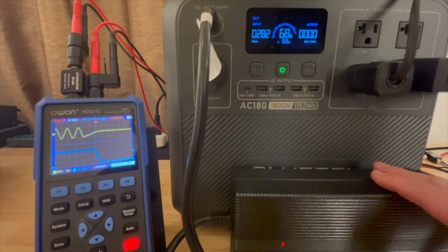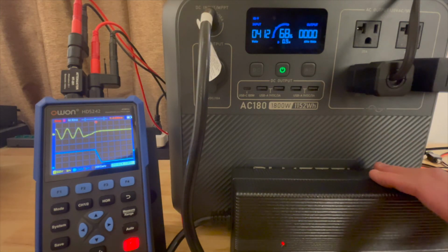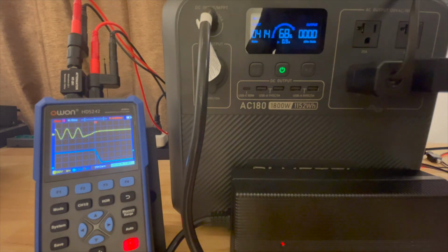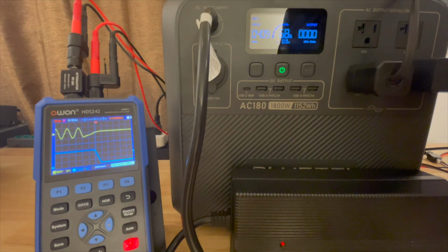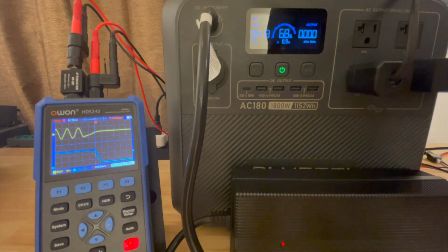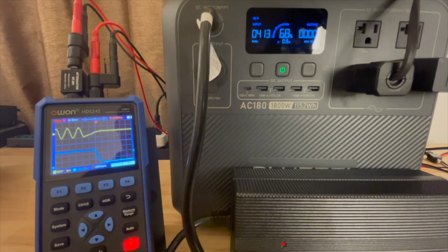So if my loads did lose power, this would have triggered. But with this type of setup, you actually don't wind up losing power even if the power fails. The downside is you're putting more load on the battery. So the offline UPS mode is better most of the time when power doesn't fail often and the load isn't that critical if it loses power for a sub-second. But if you really need it to not lose power even for a sub-second, you might want to use the online UPS mode.